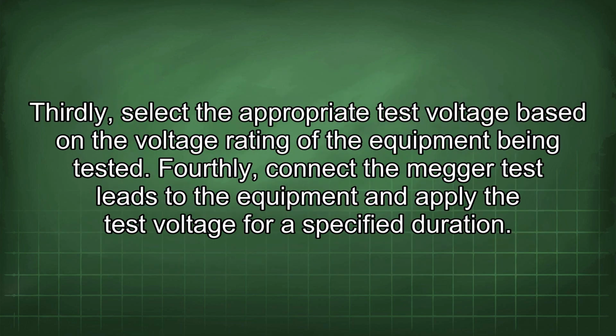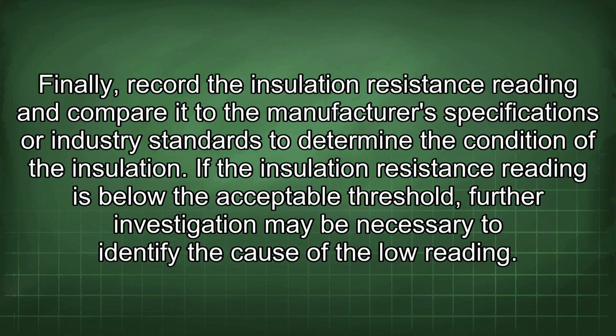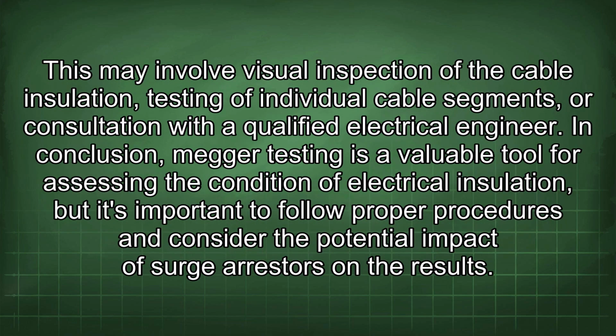Thirdly, select the appropriate test voltage based on the voltage rating of the equipment being tested. Fourthly, connect the Megger test leads to the equipment and apply the test voltage for a specified duration. Finally, record the insulation resistance reading and compare it to the manufacturer's specifications or industry standards to determine the condition of the insulation. If the insulation resistance reading is below the acceptable threshold, further investigation may be necessary to identify the cause of the low reading. This may involve visual inspection of the cable insulation, testing of individual cable segments, or consultation with a qualified electrical engineer.